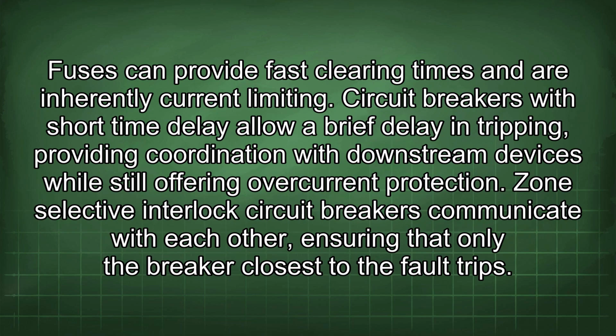Fuses can provide fast clearing times and are inherently current limiting. Circuit breakers with short time delay allow a brief delay in tripping, providing coordination with downstream devices while still offering overcurrent protection. Zone-selective interlock circuit breakers communicate with each other, ensuring that only the breaker closest to the fault trips.